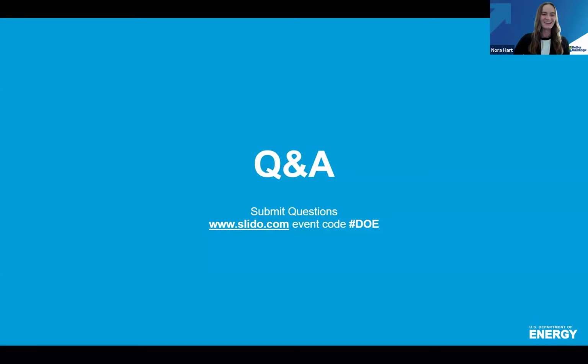That's true. So for the next set of questions, I'm going to talk a little bit about thermal energy storage. This first one is, do you see thermal systems that can serve both heating in the winter and cooling in the summer, or are they typically separate systems? So we definitely see both, and it depends on what your load profile looks like. If we can do it with a single tank, we typically call that a seasonal changeover tank. In the wintertime, it serves as hot water storage. And then in the shoulder seasons, like March and April, everyone's comfortable, and it doesn't really need to do anything.